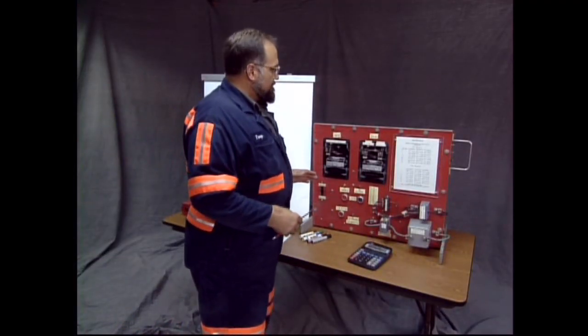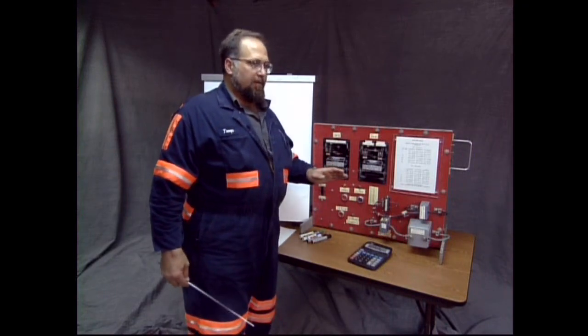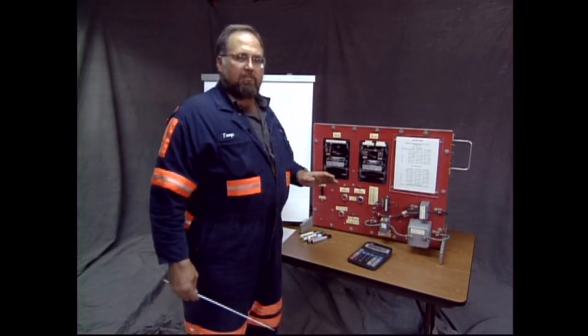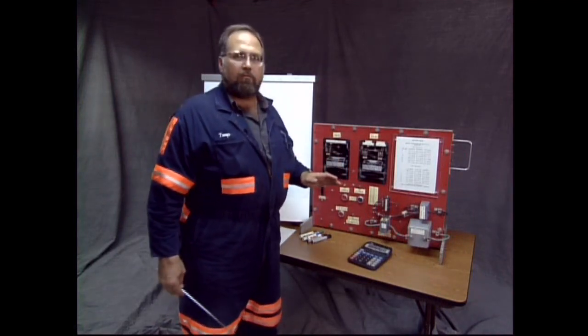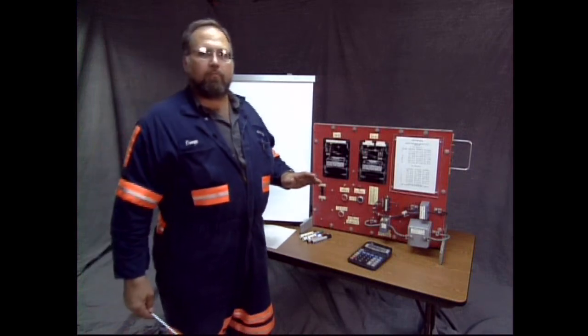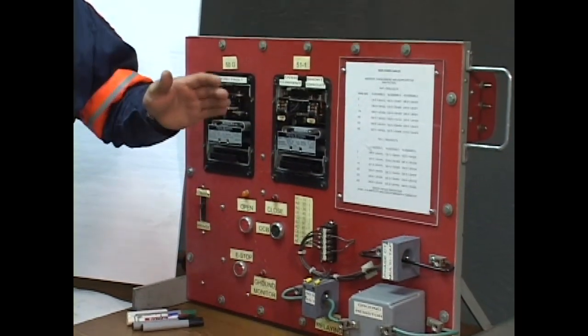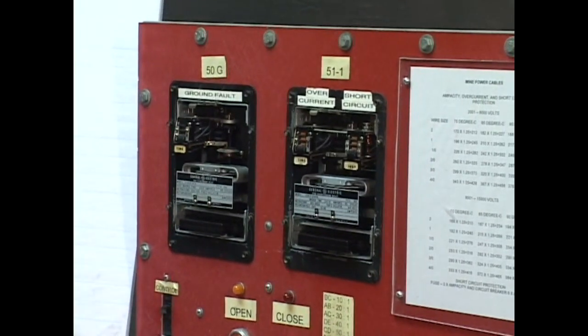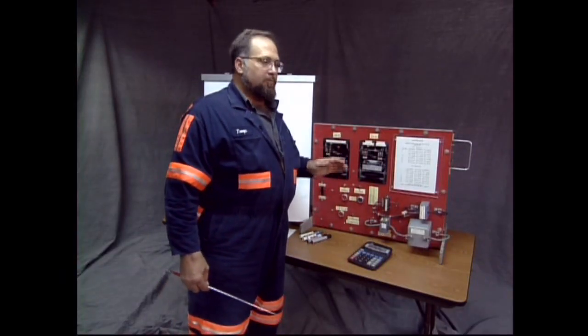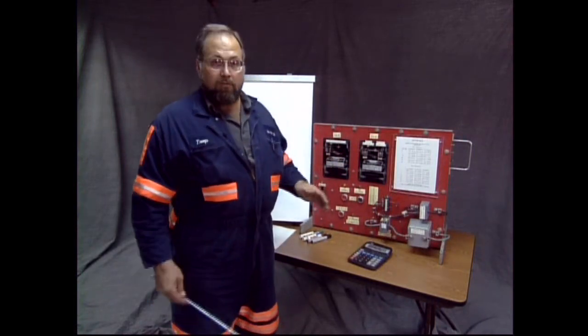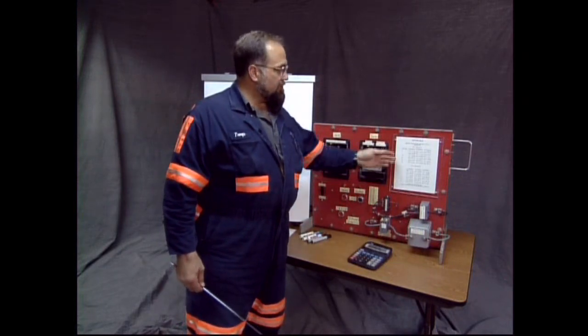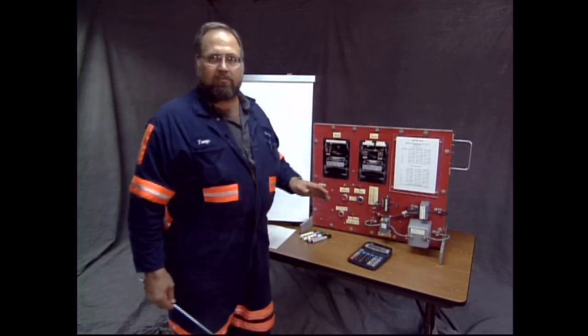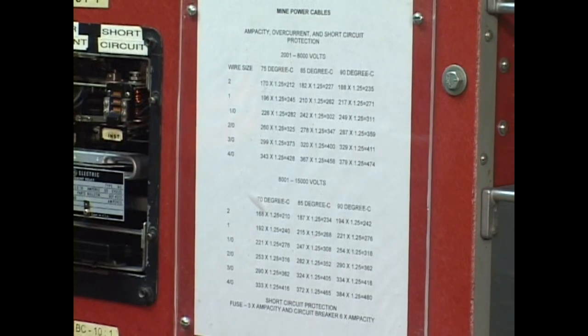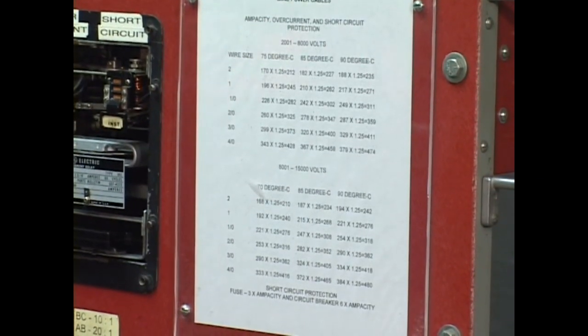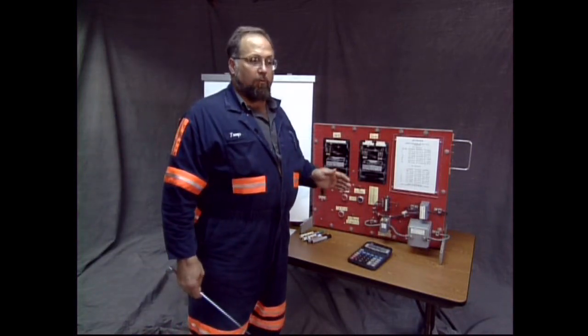Okay, we talked about all these different devices and the different protections they provide. Now let's talk about what decides our protections, what decides the level that we're going to protect, what level of current flow or what level of fault that we're going to interrupt. And with the 51-1, 2 or 3, the phase relays, that's determined by the cable size. You adjust your relays, you adjust your circuit breaker's trip levels to accommodate the size cable you're using. And there's several cable sizes listed here. And they're accepted ampacities. Okay? Now, this chart here is going to tell you pretty much all you need to know about what level you can adjust your breaker to. Now, the 50G, that's for ground fault.